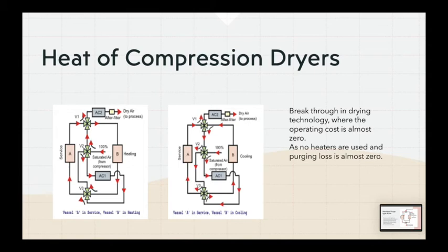Now we perform two cycles here. One cycle is of heating, another cycle is of cooling. The first cycle comprises 2.5 hours of heating, and the next cycle comprises 1.5 hours. How do we go about it? In the first process, as you have been made clear, we use dried air at a temperature of 135 degrees Celsius.